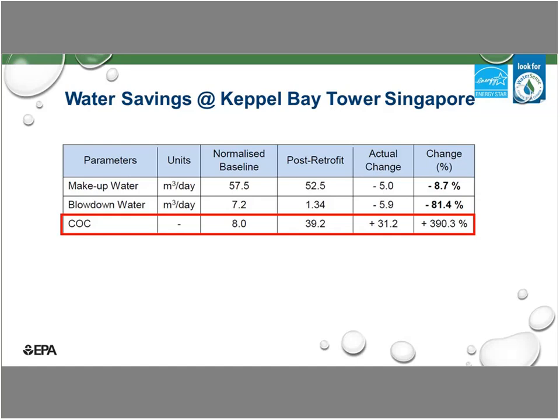With our system, our blowdown is 1.34 cubic meters per day. So we actually save 5.9 cubic meters of blowdown that they had. That's equivalent to 81.4% water saving, so this is very significant. We actually achieved 39.2 COC. This is going to help a lot on the water saving side.